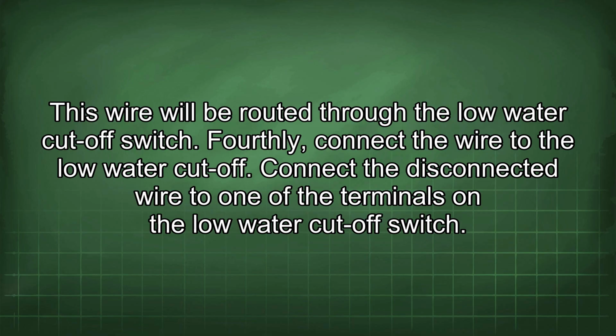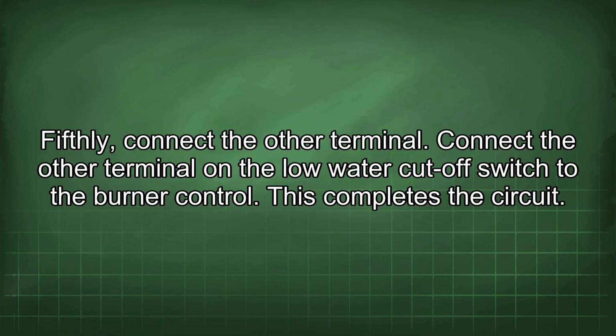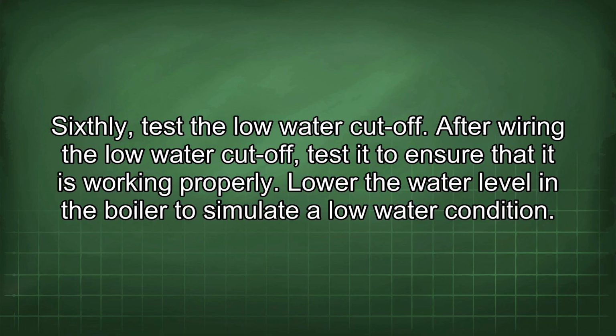Fourthly, connect the wire to the low water cutoff. Connect the disconnected wire to one of the terminals on the low water cutoff switch. Fifthly, connect the other terminal. Connect the other terminal on the low water cutoff switch to the burner control. This completes the circuit. Sixthly, test the low water cutoff.